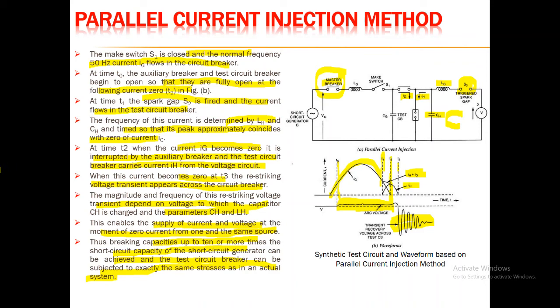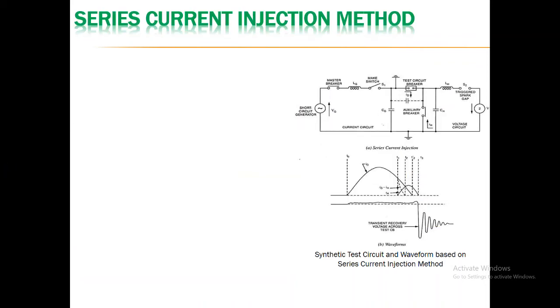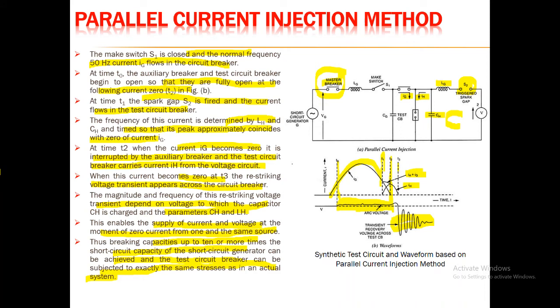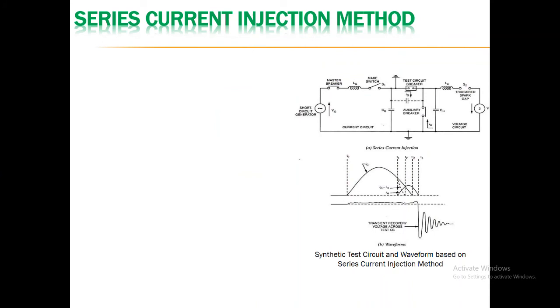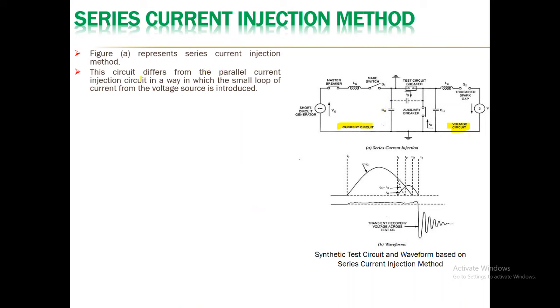The last method is the series current injection method. In the previous parallel case, the short circuit generator circuit and the high voltage circuit were connected in parallel. In the series current injection method, both circuits are connected in series — this is the current circuit and this is the voltage circuit, both connected in series.